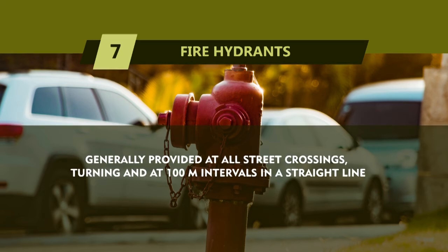These are generally provided at all the street crossings, turnings, and at 100-meter intervals in a straight line. These are also provided in commercial and institutional installations to ensure that water can be made available at the time of fire in as close vicinity to the buildings as possible. Whether it's a flush type fire hydrant or a post type fire hydrant, they are both provided directly on the water main line as mentioned earlier.